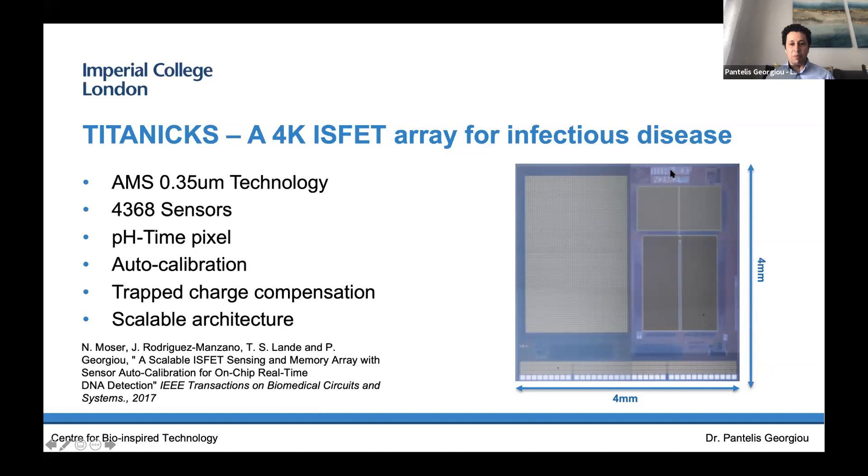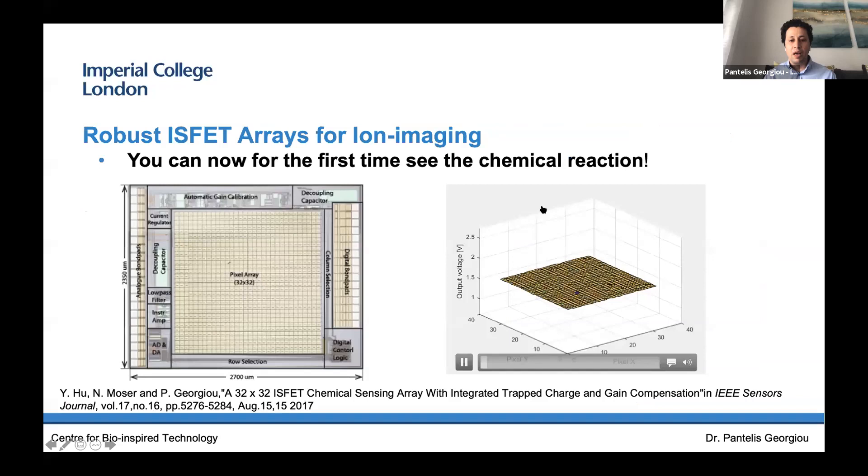We've proven in the past that we can get reliable detection of DNA using what are called ion-sensitive field effect transistors (ISFETs) — similar to the MOSFET transistor. We turn them into pH sensors and using our amplification chemistry, we detect the presence or absence of DNA. Here's an example of our flagship chip that we're using for infectious diseases — we call it Titanicks, designed by two of my PhD students and postdoc Nick Moser. It's got 4,000 sensors. What's unique is we've also used microelectronic circuits to make it adaptive, so it can compensate and adapt to its environment, giving very robust and reliable results.